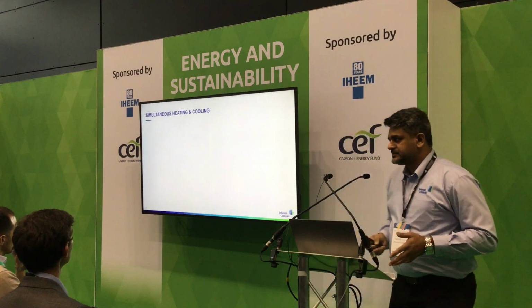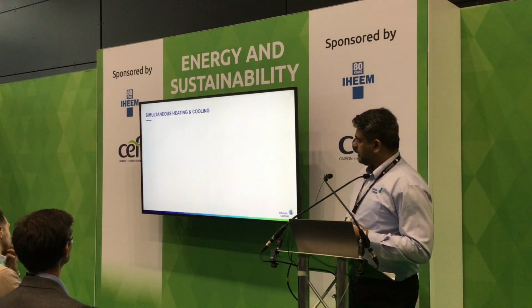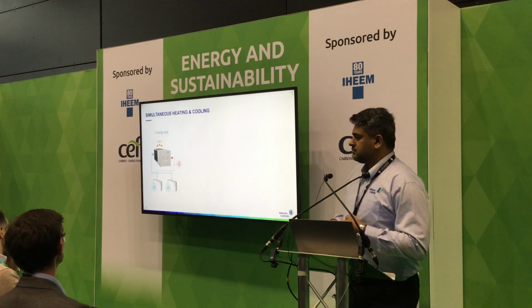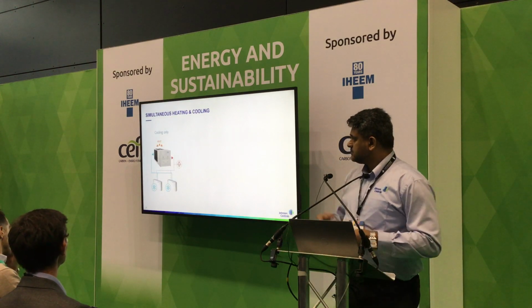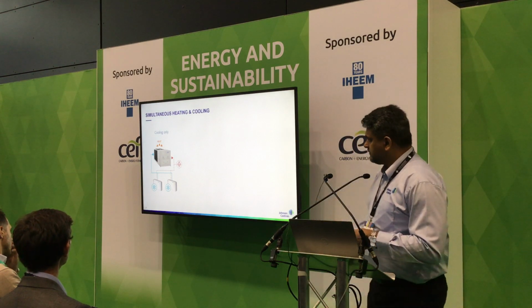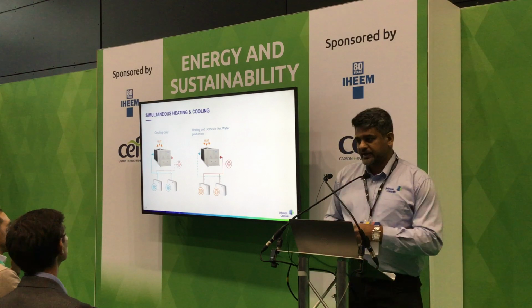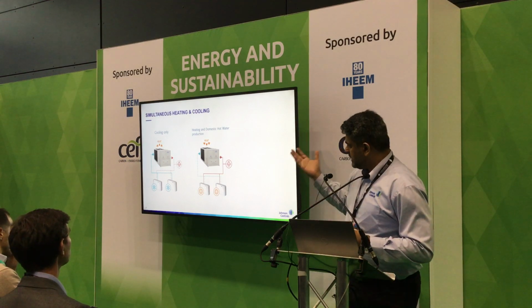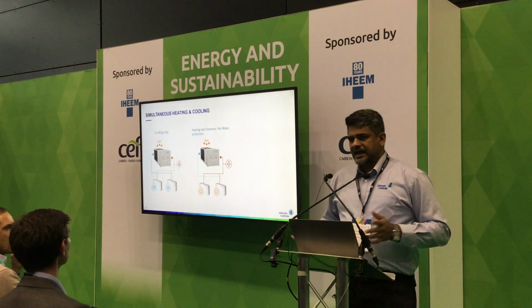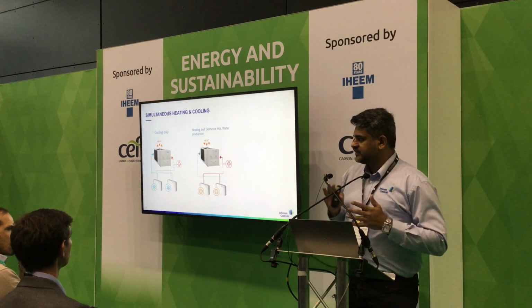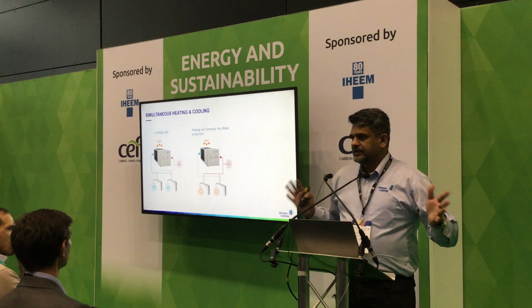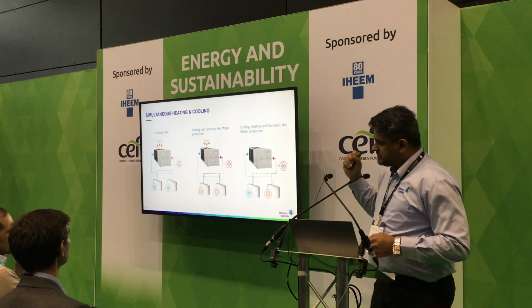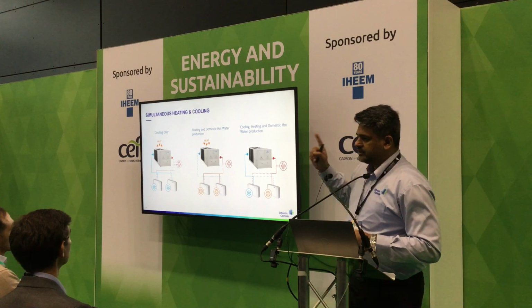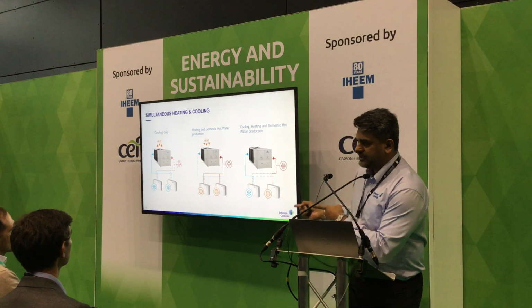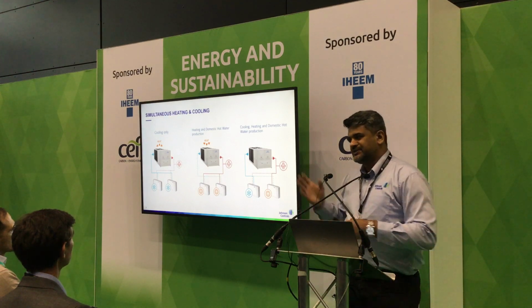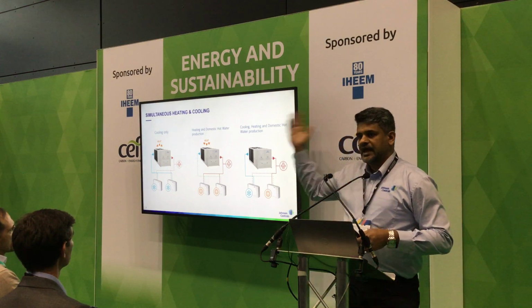Simultaneous heating and cooling. This is a 4-pipe air source heat pump product. From the same unit, depending on what time of the year it is, you can get cooling only, so it rejects heat into the atmosphere. You can use it for heating only, so it draws heat from the source and utilizes it for heating. And as is the case in most of the facilities here, you will have times when you need both heating and cooling in the same building. That same unit can give you both heating and cooling, transferring the energy from each circuit and driving the efficiency of this particular equipment all the way up to 8, 9.